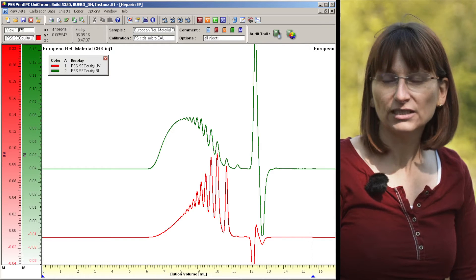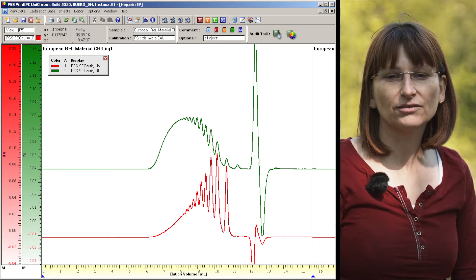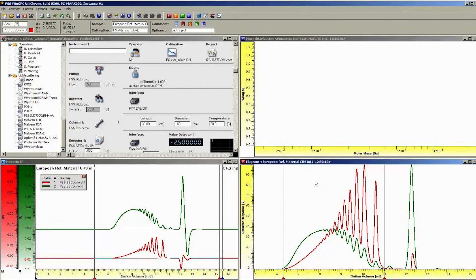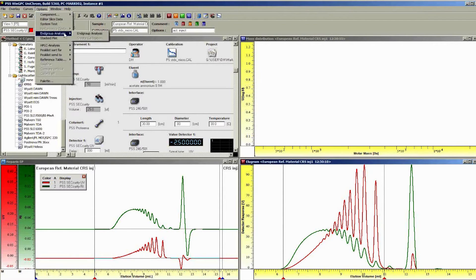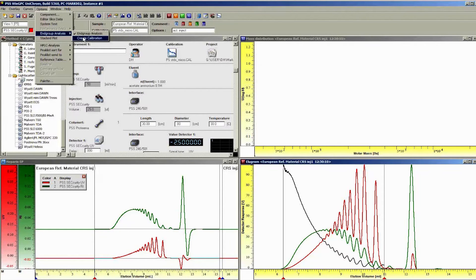For both pharmacopoeias, you run the calibration sample first. In the case of EP, you get two traces: a red trace belonging to the UV signal, detecting each single end group just once, and a green trace from the refractive index detector where you see each repetition unit. The key is to extract the calibration curve from these two traces using end group analysis, allowing you to construct a GPC/SEC calibration curve from just one sample. It's important to realize that you're getting accurate molecular weights because you're using heparin to calibrate and later to analyze.